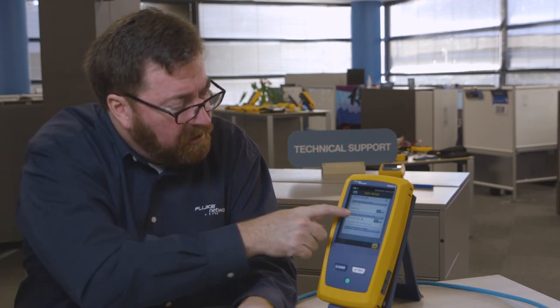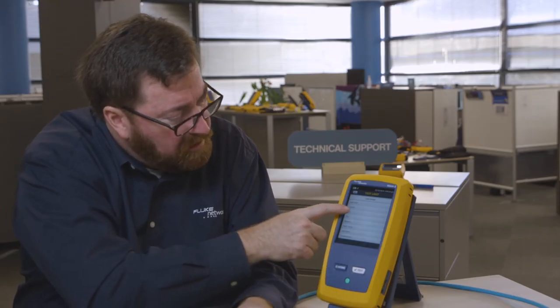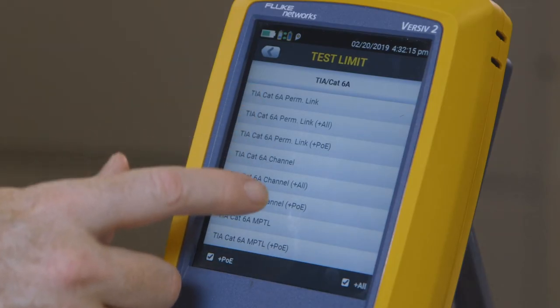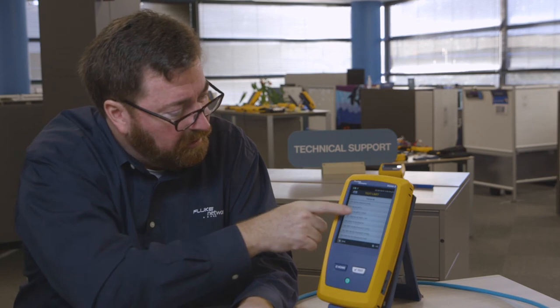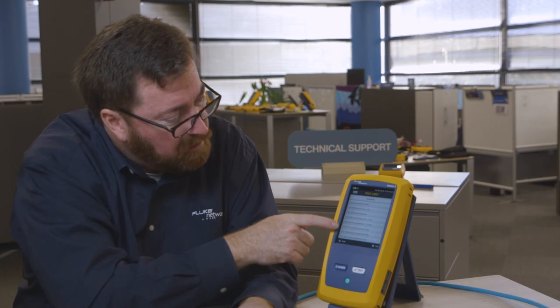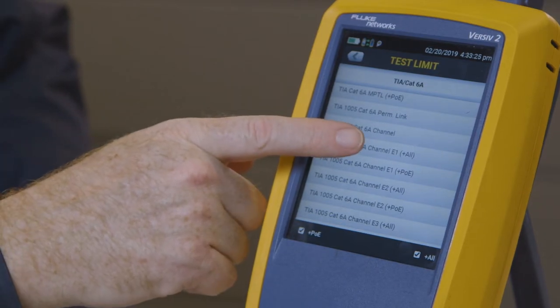If the shield test is enabled, we'll check for continuity. Now for the test limit — I'll choose more down in the bottom corner. Let's start with the TIA limits and look at Category 6A. Here are our 568 limits with channel and permanent link, and our MPTL limits. Then we get into the 1005 limits, where you'll see there's a permanent link and a channel test, and then E1, E2, and E3 options. These correspond to environments with a MICE rating of E1, E2, or E3.